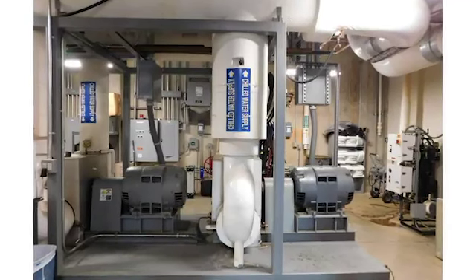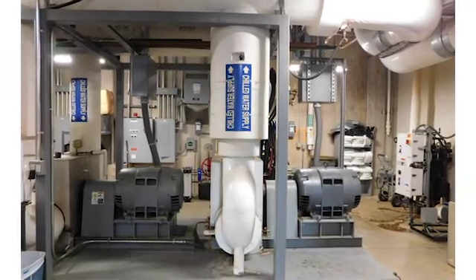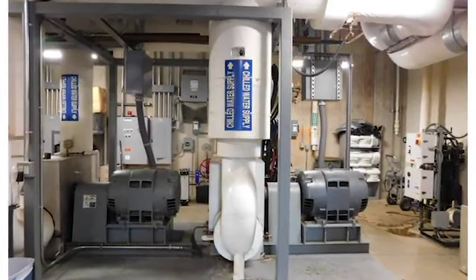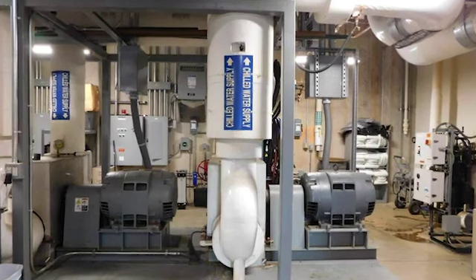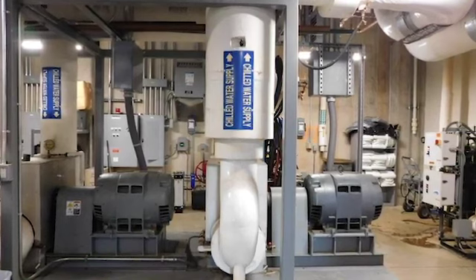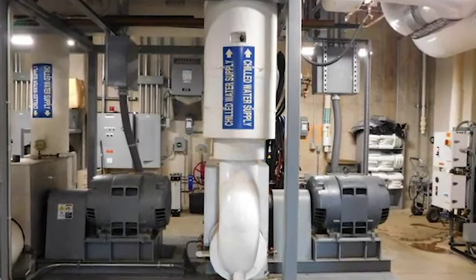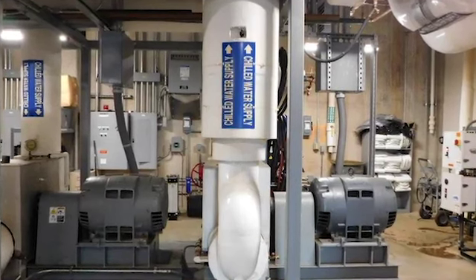The secondary loop will take the water from the chillers or the TES tank and then send it back to the hospital to the various air handlers. What's really cool is the TES tank can serve the hospital exclusively. We can also reconfigure the absorber to be a direct provider of chilled water to the hospital and blend its output with the primary flow coming from the TES tank. So even though the output from the absorber might only be 45 degrees, the TES water's at 39 and an overwhelming flow.